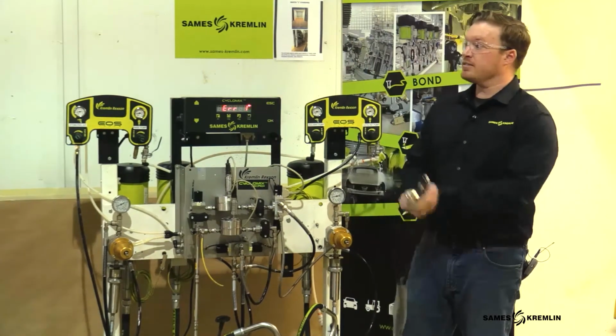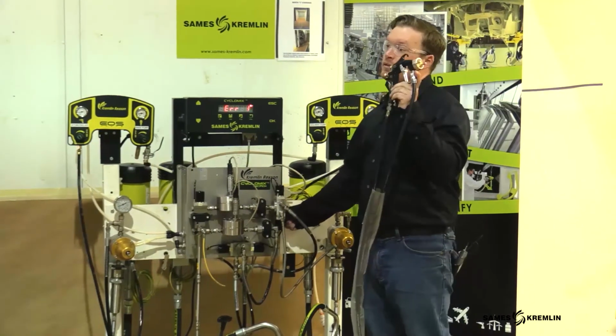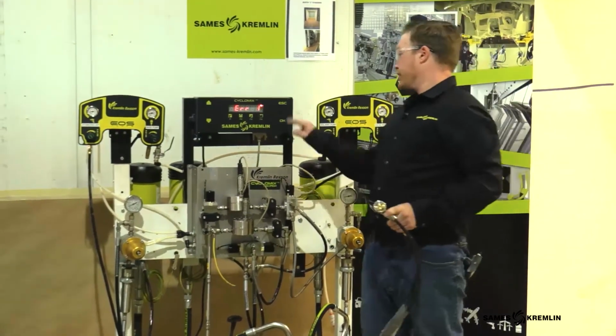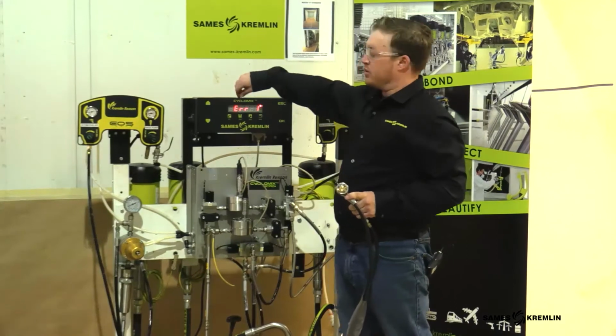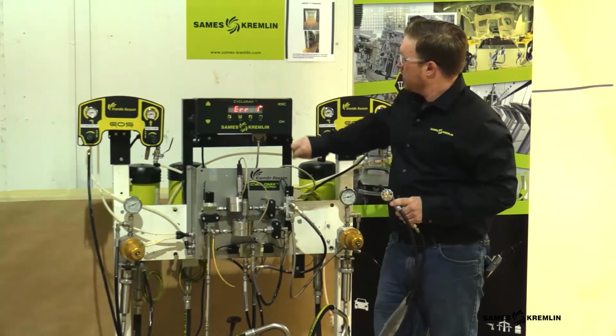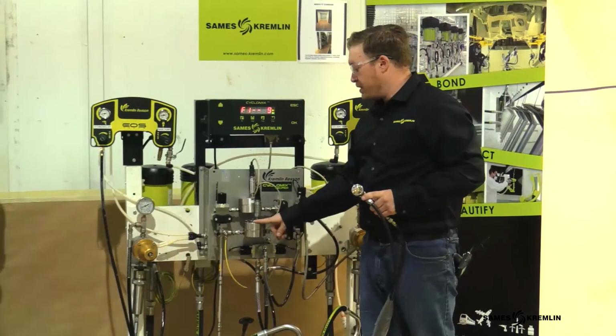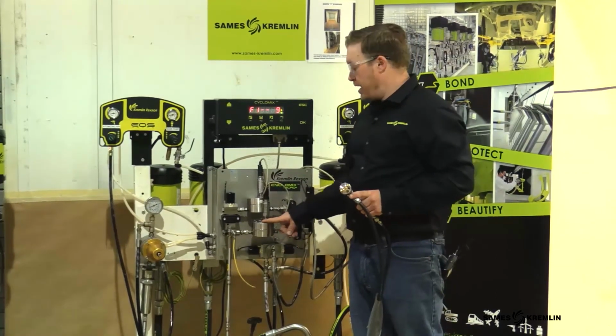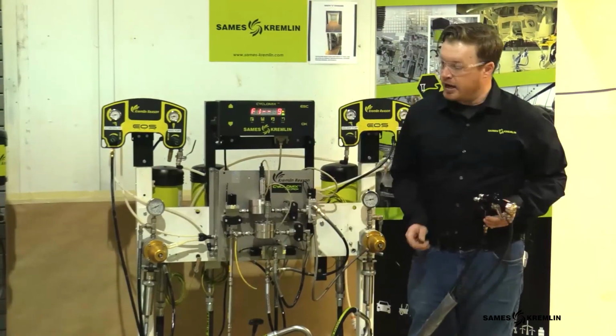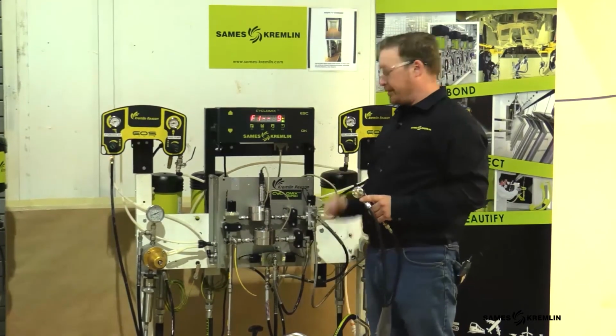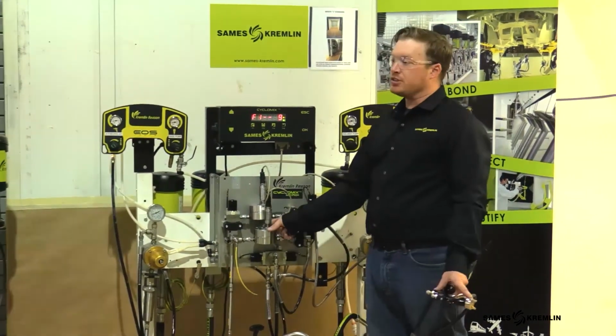Error 1, because that airflow switch closed, gave one of those feedback signals to the controller, but in fact the flow meter was not spinning. Obviously I was not spraying, the gears were not turning. It thinks that there is a blockage in the flow meter.